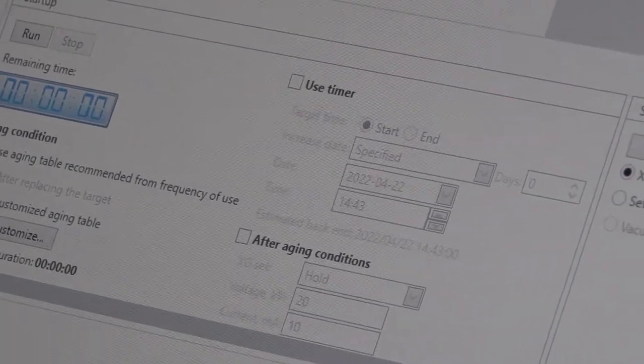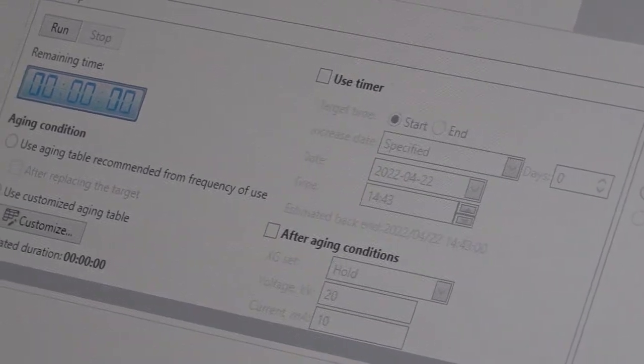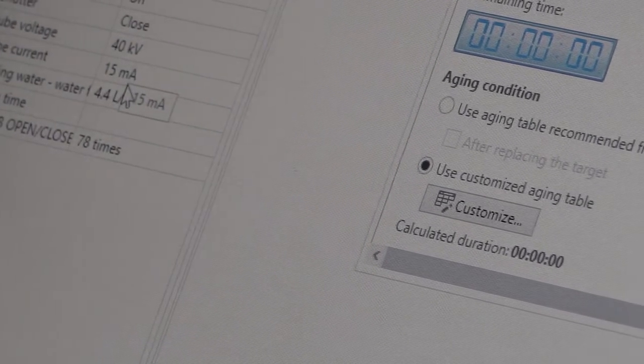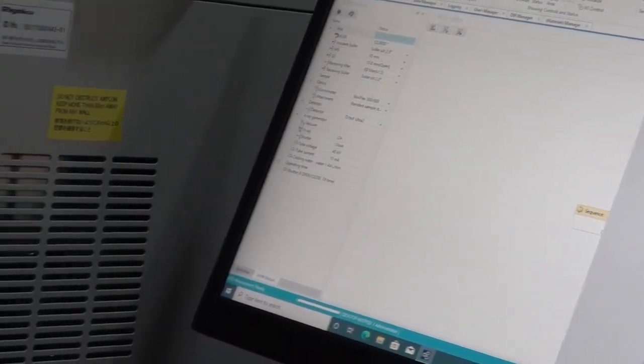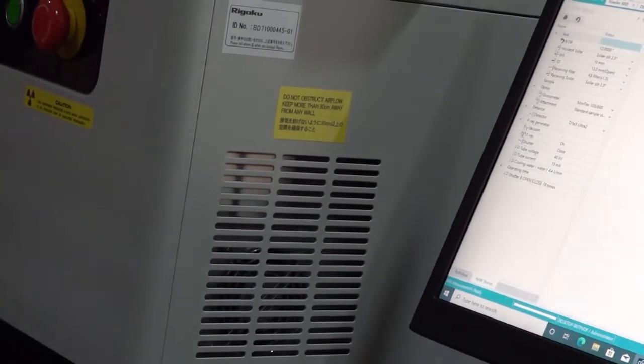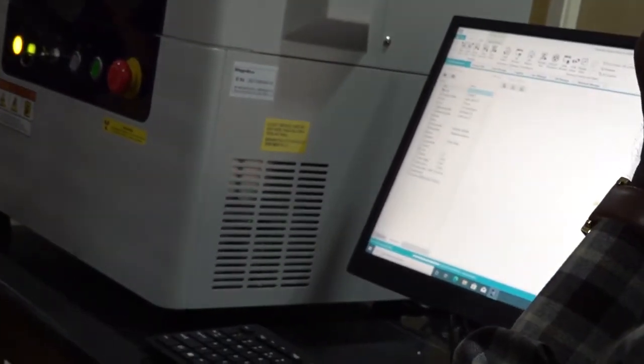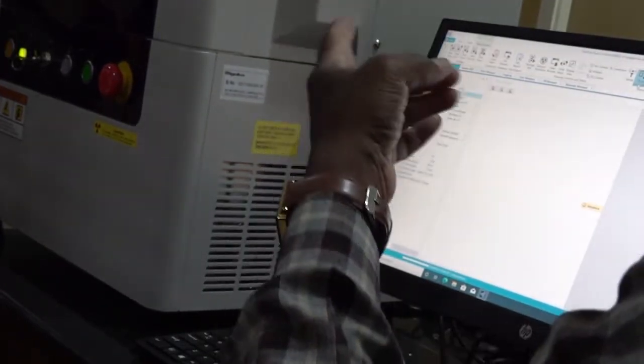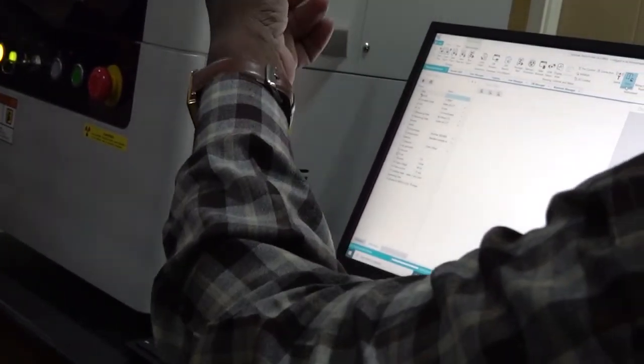Okay, this is completed now. So you can see the power now, 40 and 15. So 40 into 15 is 600 watts. You can close this and open the door even through the software. Here door lock open is there. Just click this, see, you can open the door. Now you have to open the door and keep your sample there. The standard is there. You remove it and keep yours.